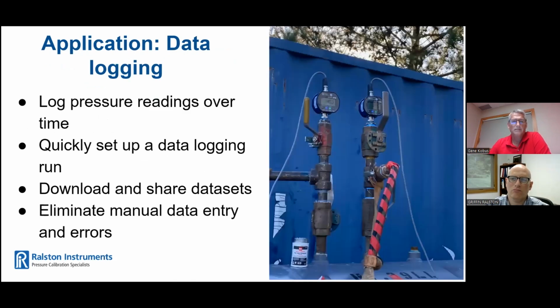Another excellent application is data logging. The LC20 can digitally log pressure readings over time, allowing for analysis and troubleshooting of pressure-related issues. A single channel at 1 minute interval can log 14 hours and 29 minutes. Our dual channel model at 1 minute can log 9 hours and 46 minutes. You can improve your workflow by easily logging, downloading and sharing data sets via email or other file sharing apps. You can eliminate manual data entry and reduce data entry errors.